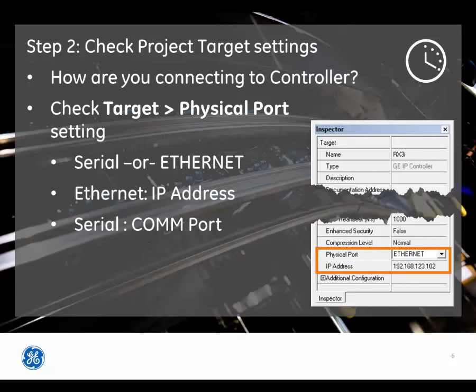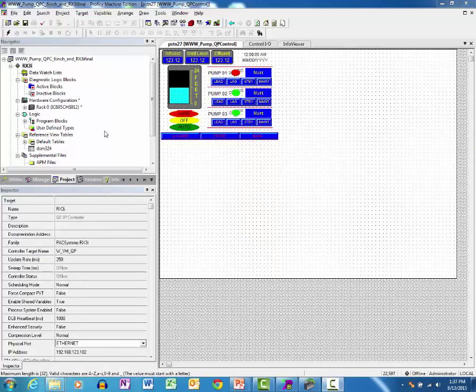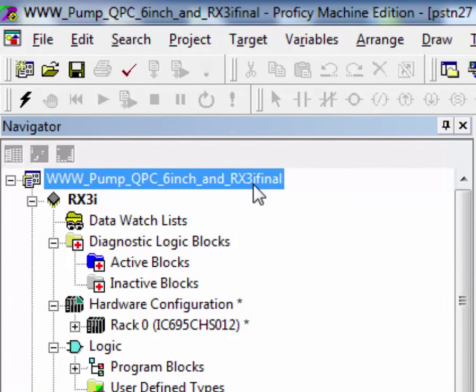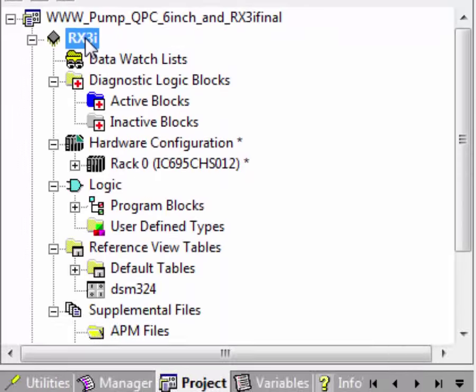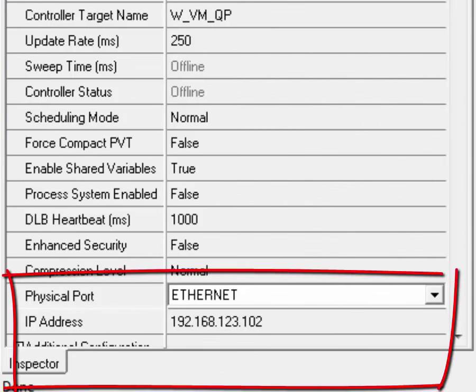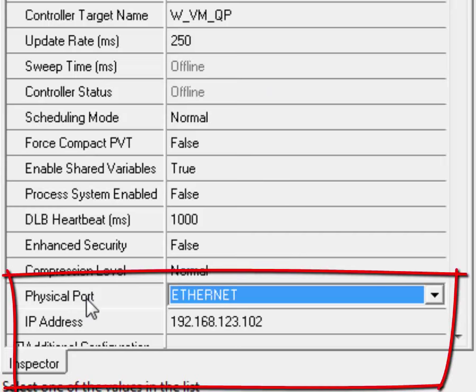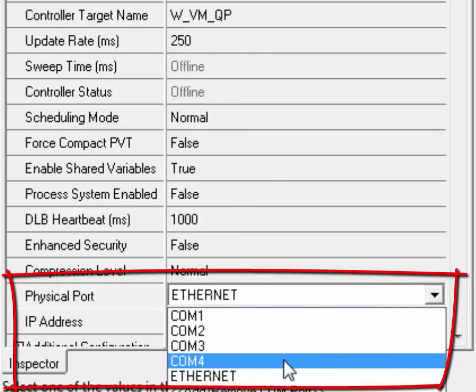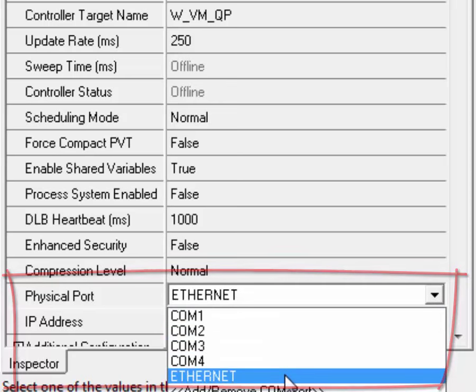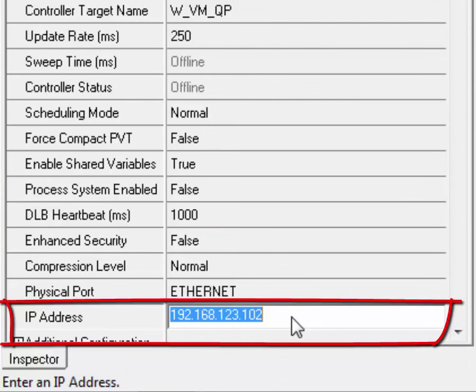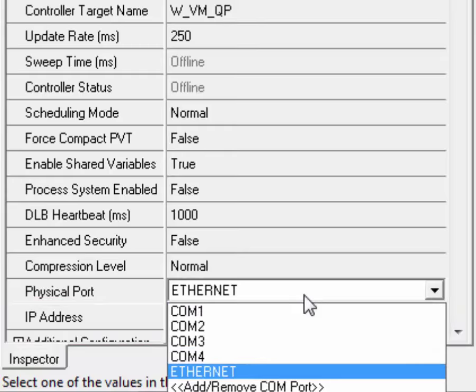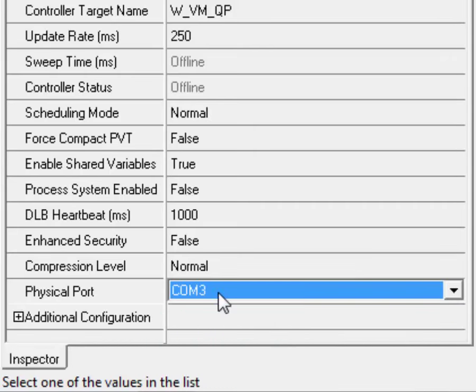Let's take a look at how to perform these operations. For the Machine Edition project that you want to use with the controller, examine the controller target property's physical port parameter. This parameter determines how the programming software attempts to connect to the controller. As you can see, the physical port parameter has Ethernet and serial COM ports as options. If Ethernet is selected, an IP address is shown — it must match the IP address currently configured in the controller. If a COM port is selected, the software will use this port to attempt communications with the controller.